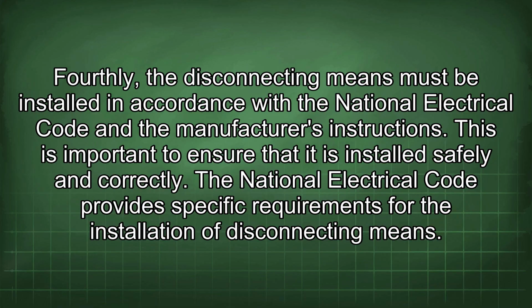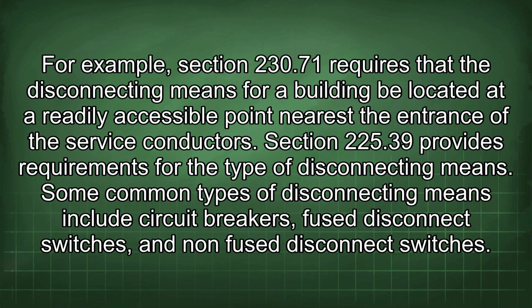The National Electrical Code provides specific requirements for the installation of disconnecting means. For example, Section 230.71 requires that the disconnecting means for a building be located at a readily accessible point nearest the entrance of the service conductors. Section 225.39 provides requirements for the type of disconnecting means.